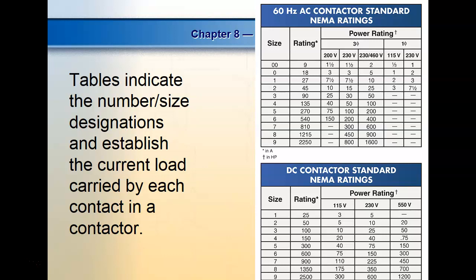This is pretty important to know, and it's going to be on the label of the contactor. You're going to have it on the control relay and on the contactor. They don't put the current that you can push through those contacts on the side. So you can start right here to figure out how much you can run, right? Everybody okay?